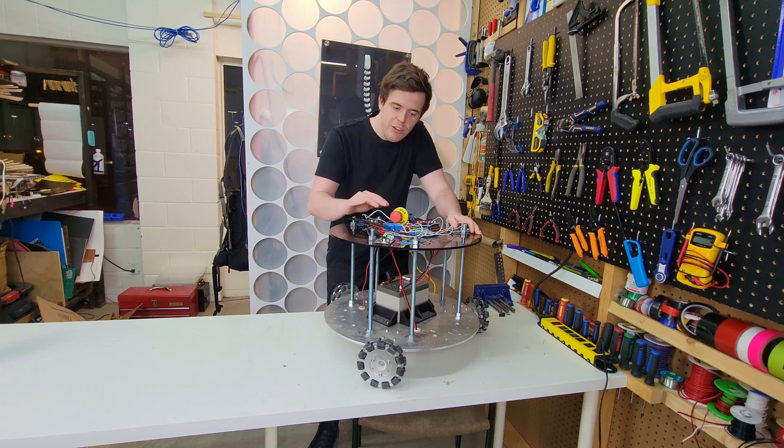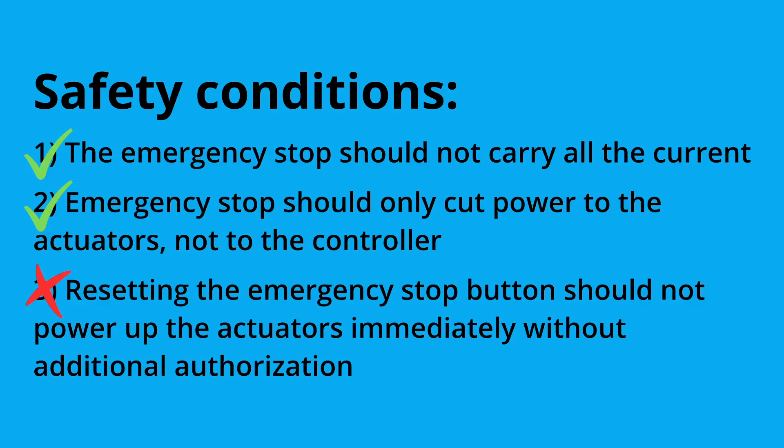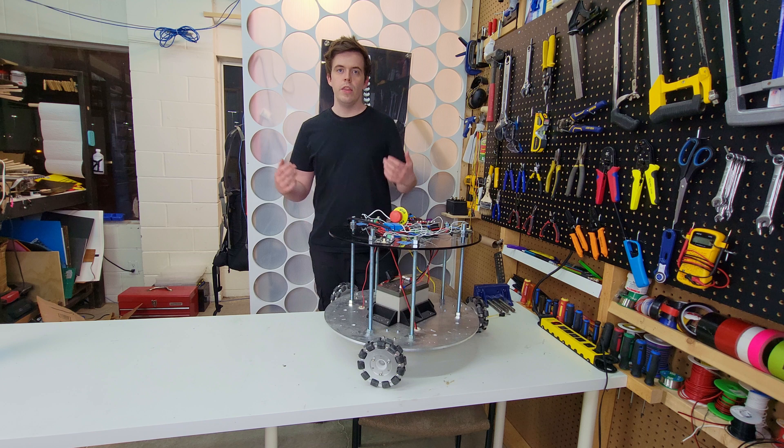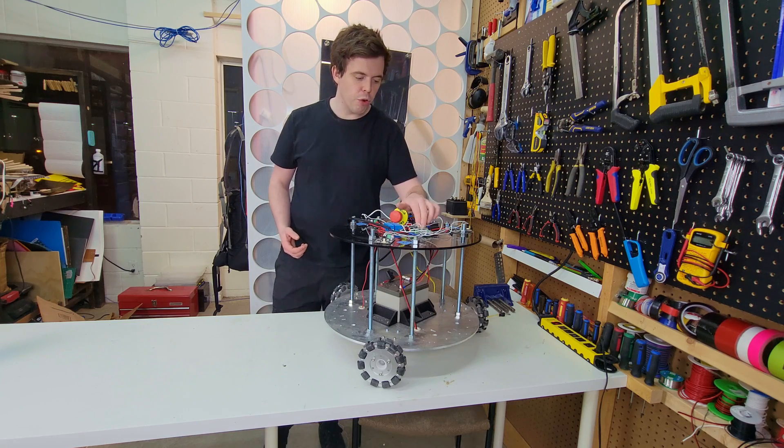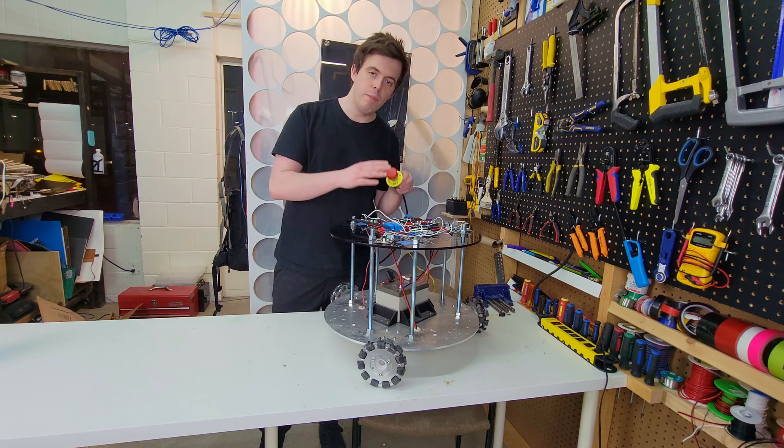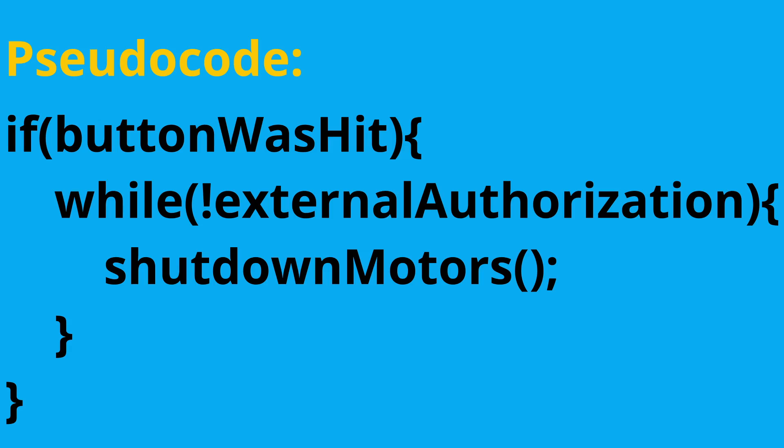Alright, so with this we've met the first and second of our safety requirements. But the final requirement states that resetting the emergency stop button should not power up the actuators immediately without additional authorization. This means we need some way for the controller to know when the emergency stop button has been hit. If it was hit, update the motors to stop, and don't start them back up until external authorization has been given by the operator.